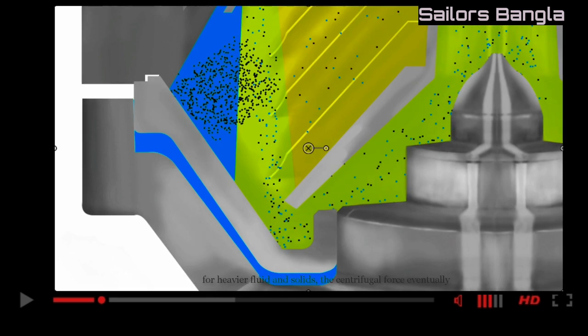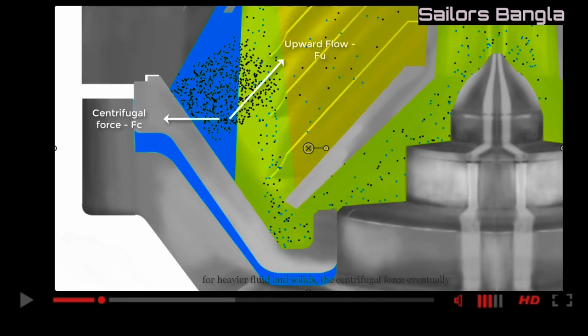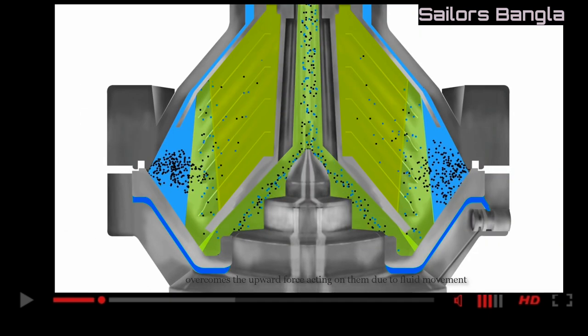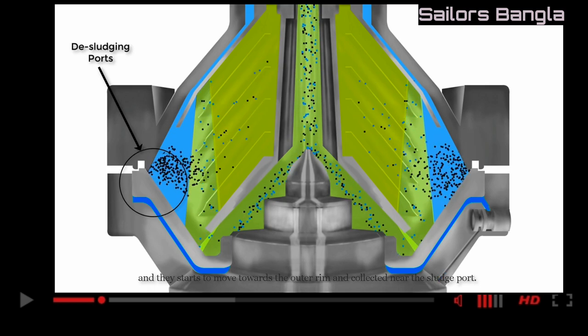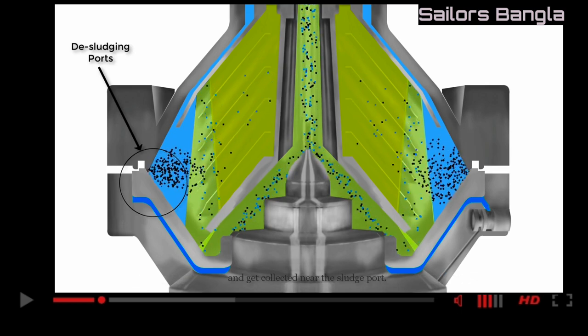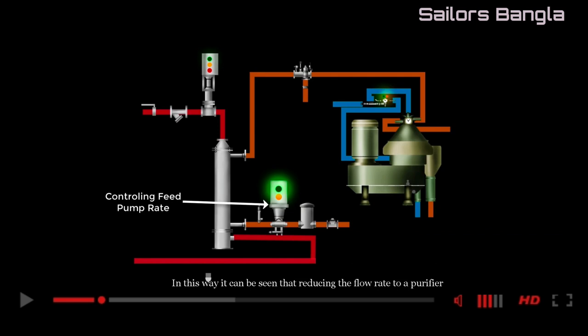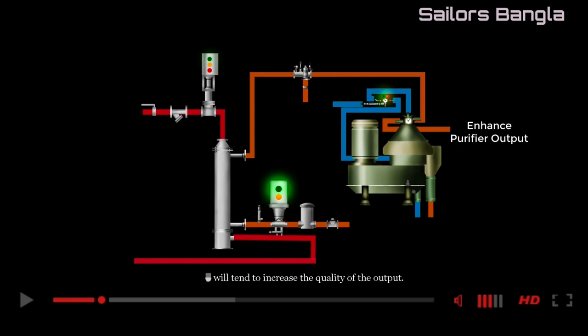For heavier fluids and solids, the centrifugal force eventually overcomes the upward force acting on the particles due to fluid movement, and they start to move towards the outer rim and get collected near the sludge port. In this way, it can be seen that reducing the flow rate to a purifier will tend to increase the quality of the output.